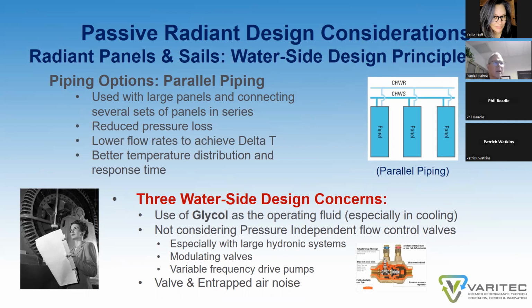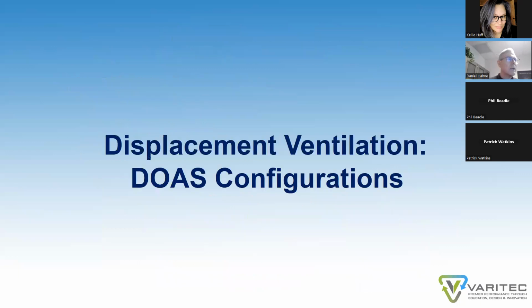There are 3 waterside design concerns with a passive radiant system. Use of glycol as an operating fluid, especially in cooling, is not a good idea. Not considering the use of pressure-independent flow control valves, valves that can always assure that the necessary water is getting to the radiant component regardless of fluid pressures within the piping scheme. And then, of course, valve and entrapped air noise you need to be aware of and how to address that. That can be addressed in the actual design of the water system and taken care of.